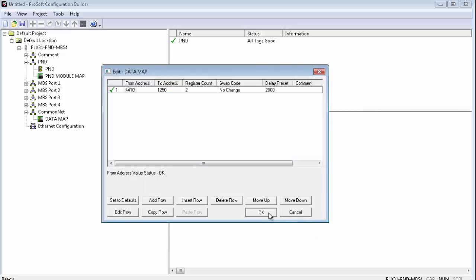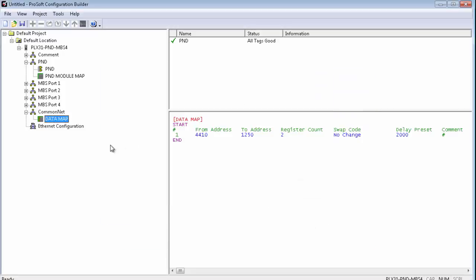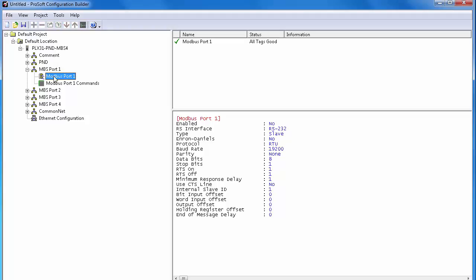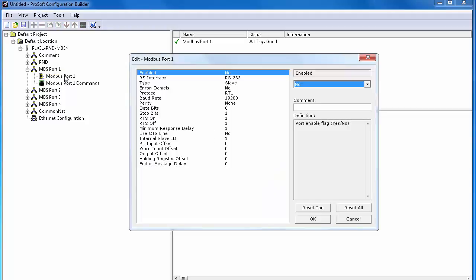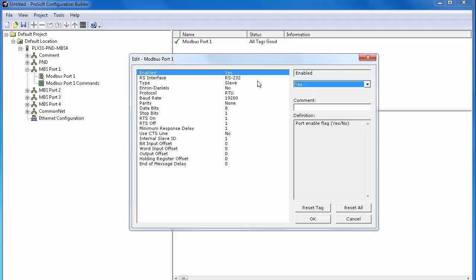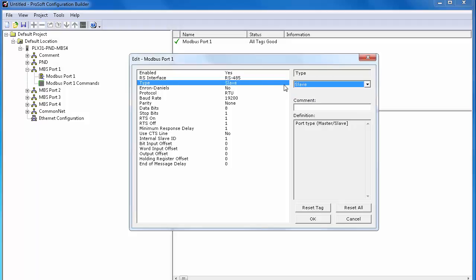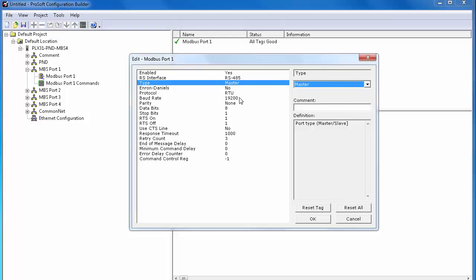Now, we can move on to configure the MBS port. Expand MBS port 1 under PLX 31 PND MBS. Right-click on port 1 and select Configure. And when the edit window opens, we can see all the configuration options available for our MBS port. First, we'll have to enable the port. Here is the RS interface. We'll go with RS-485 for this application. The type will be a master. And protocol will be RTU.